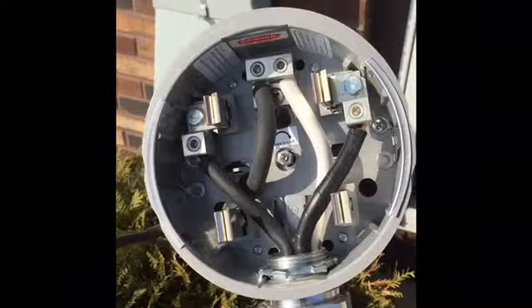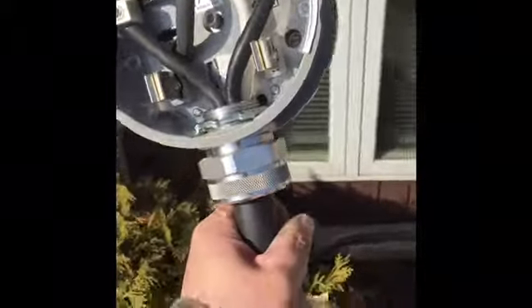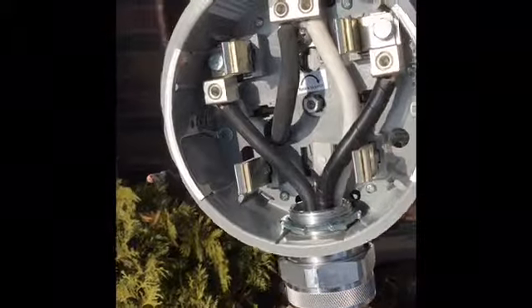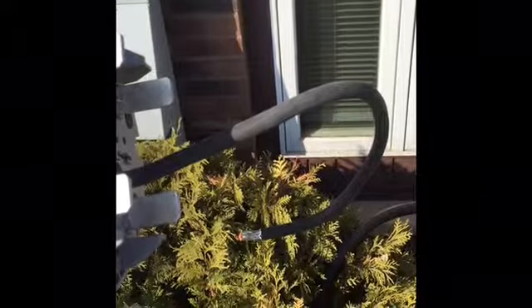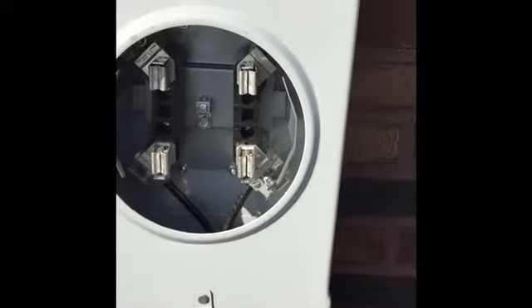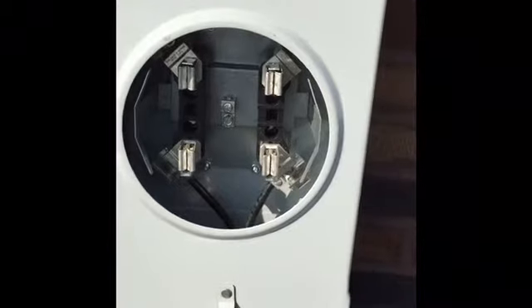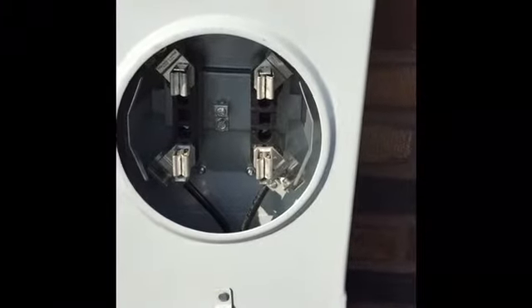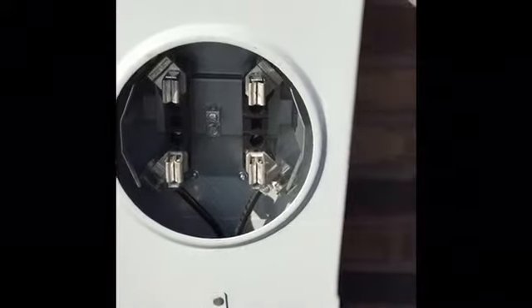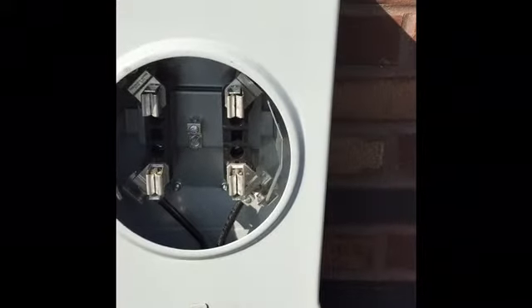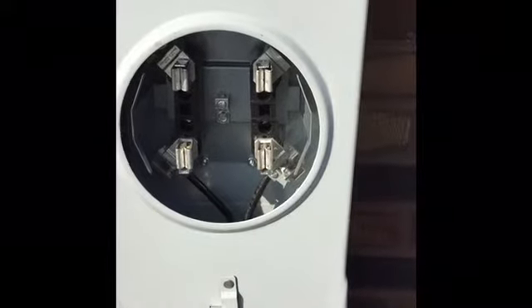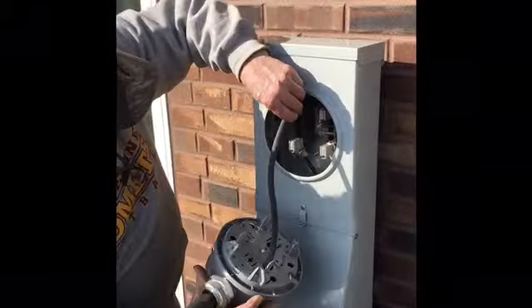Okay, the next step, what we're going to do is take our meter head adapter that's hooked up to a 15-foot cable to the cart there, and we're going to connect a neutral pigtail that's in the back of the meter head adapter here. We're going to connect that to the neutral bus bar in the meter socket, and in this case we have a center mount one, but essentially the lug that's connected, a lot of them are connected to the side of the meter can, or some of them are on the meter socket base itself, like the one shown here. Okay, so we're connecting that in there right now.